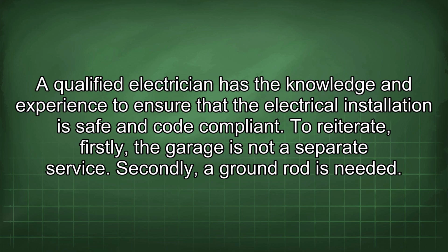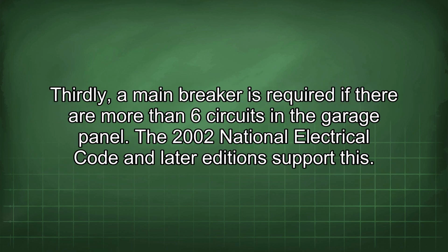To reiterate, firstly, the garage is not a separate service. Secondly, a ground rod is needed. Thirdly, a main breaker is required if there are more than 6 circuits in the garage panel. The 2002 National Electrical Code and later editions support this.